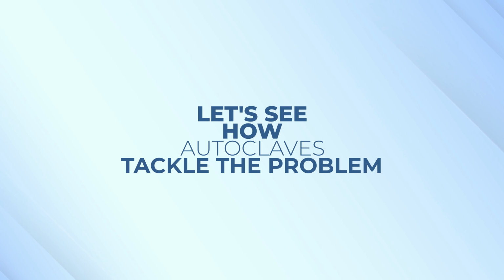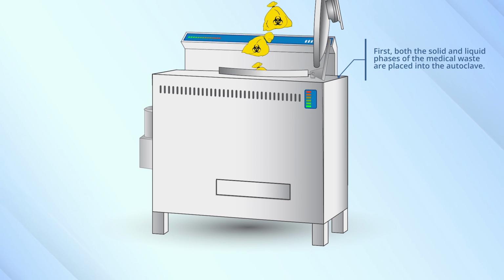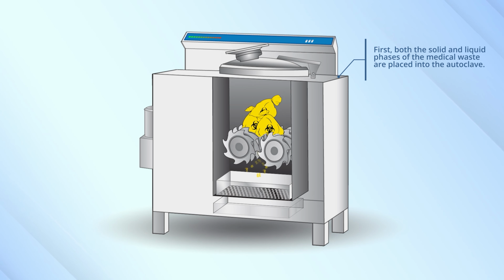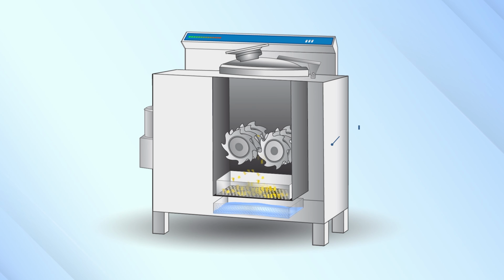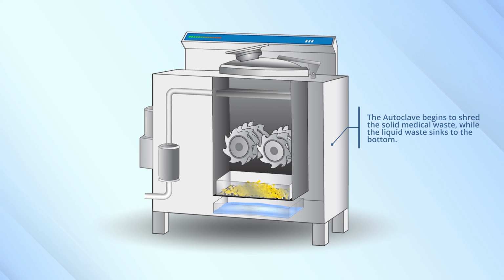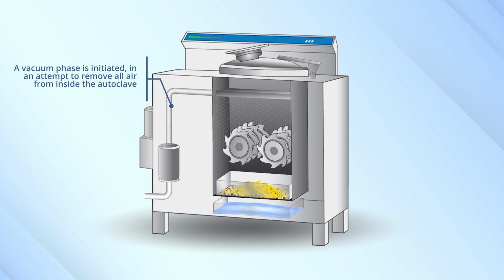Let's see how autoclaves tackle the problem. First, both the solid and liquid phases of the medical waste are placed into the autoclave. Then, the autoclave begins to shred the solid medical waste, while the liquid waste sinks to the bottom. A vacuum phase is initiated in an attempt to remove all air from inside the autoclave. This is to ensure that the sterilization steam penetrates all surfaces of the solid waste. Any remaining air pockets would prevent the steam from effectively sterilizing the waste.